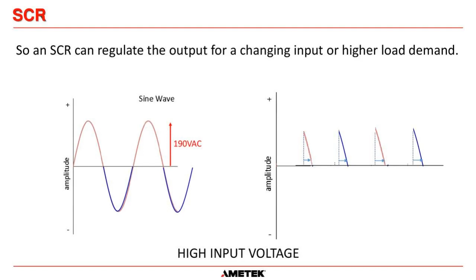So now we're going to move on to the IGBT and how it's used inside a UPS. The SCRs are used inside the rectifier circuit, and the IGBTs are used inside the inverter. And sorry if I didn't clarify this - a rectifier converts AC to DC, and an inverter converts DC to AC.